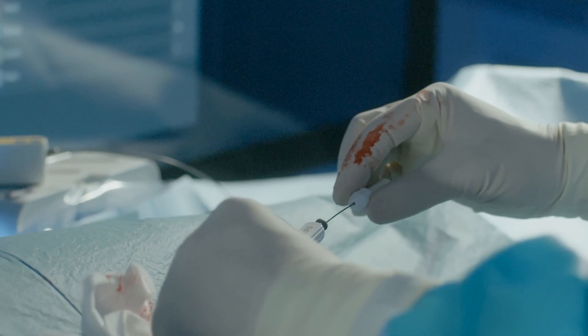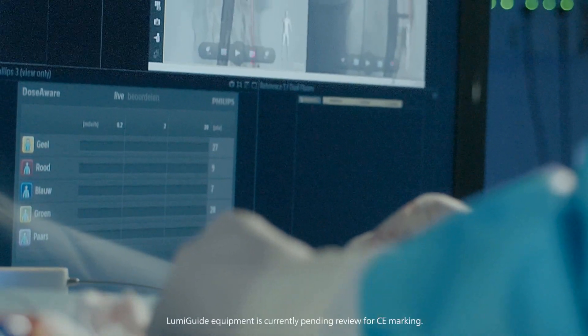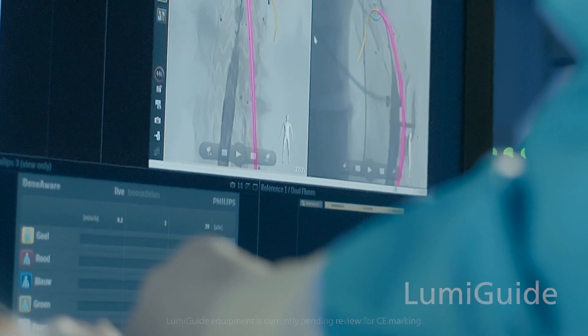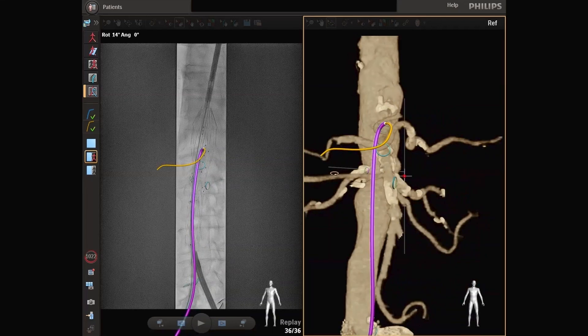Thanks to these strong collaborations, we are proud to introduce Philips LumiGuide, powered by Fiber Optic RealShape technology. LumiGuide offers real-time, full-shape 3D device visualization from all angles — and remarkably, using light instead of x-ray. It allows interventionalists to see more while navigating to target vessels, enabling them to perform procedures rapidly while further reducing radiation.